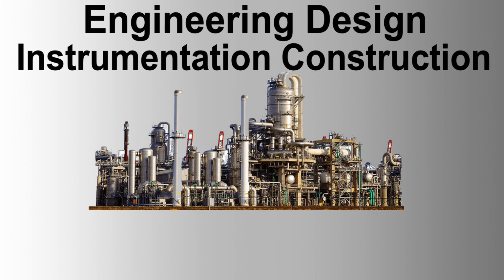Technical requirements, instrument piping. Instrument piping and tubing. Instrument piping and tubing to be installed can be classified in the following categories: air supply piping, transmission signal tubing, instrument impulse piping. Instrument piping and tubing shall be routed so that they are kept as short as possible, consistent with good practice and accessibility. Do not obstruct traffic through the plant. Do not interfere with the accessibility or removal of equipment, e.g., pumps, motors, exchanger bundles, valves, etc. Avoid hot environments and potential fire risk areas.